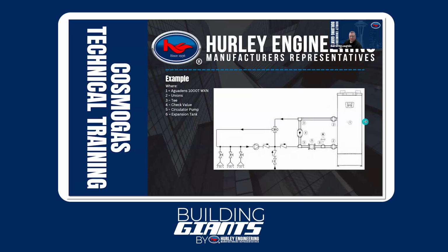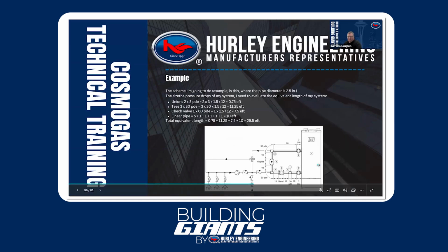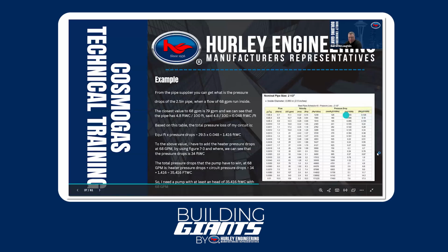Pretty straightforward. Yeah. So now once we've done that, we've got the pipe size correctly. Now we're going to do a pressure drop, because we need to see what kind of head loss this adds to our heat exchanger. We'll count up all of our fittings: the loss through the pump, the elbows, the T's, the check valves, unions. You can get charts online, or you might already have the charts, that tell you the equivalent feet of pipe for the head loss associated with each. So what we've done here is gone through and seen, okay, we've got 5 feet of pipe here. This union has 3 feet of equivalent pressure drop. This T has 30 feet of equivalent pressure drop. Then we have another 3 feet of pipe, and so on. We've taken all the equivalent feet of pressure drop through all of them and found we have a total of 29.5 equivalent feet of 2.5 inch pipe. If we do the math on that using readily available charts, we come out to 1.416 feet of head loss.